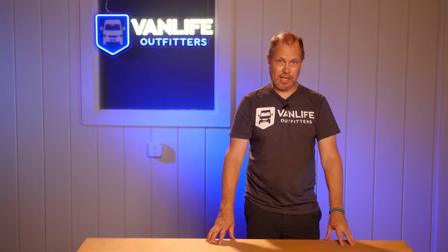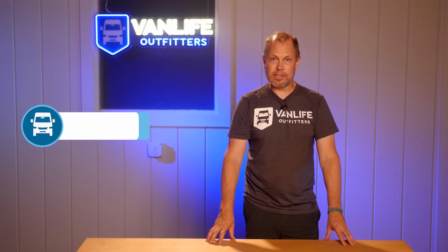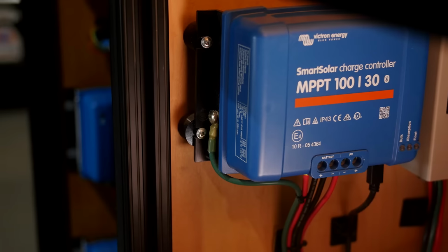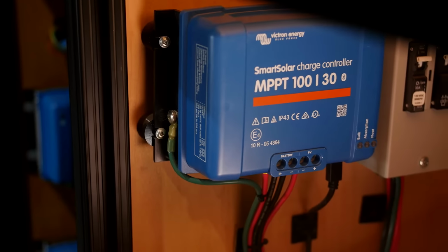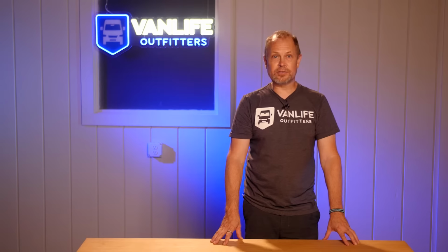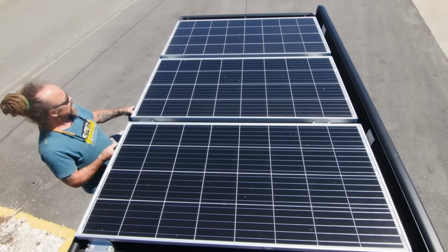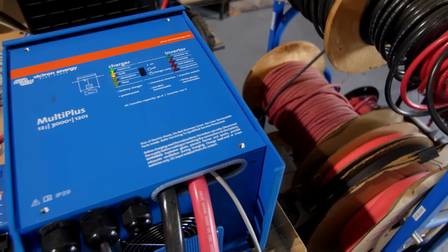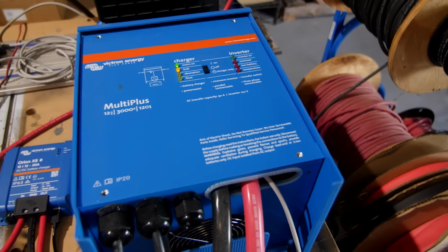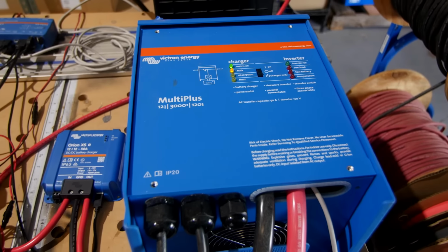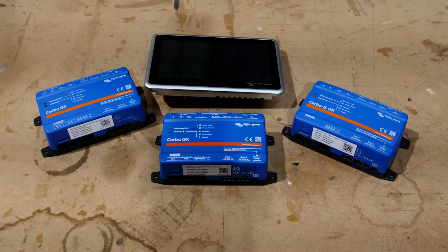DVCC is a sophisticated way to control charging your batteries in a coordinated way where all of the compatible chargers work together and are aware of what each other are doing in terms of charging, voltage, and optionally temperature. Also, in our testing, it appears to control priority so that, for example, your solar array can be the first priority for charging, maximizing its capability, while the other chargers, like a multi-plus inverter charger, produce less to maximize the free power over metered power.